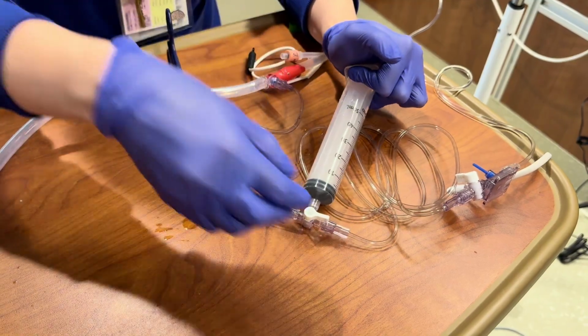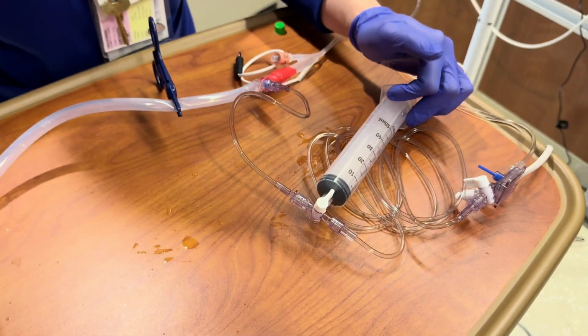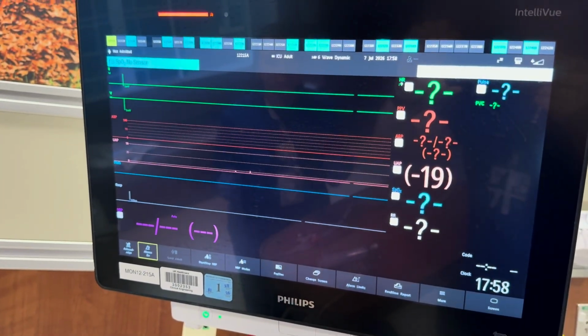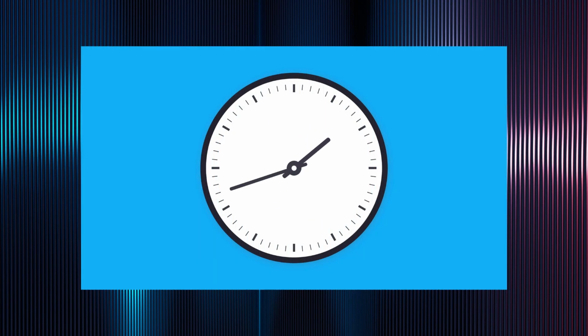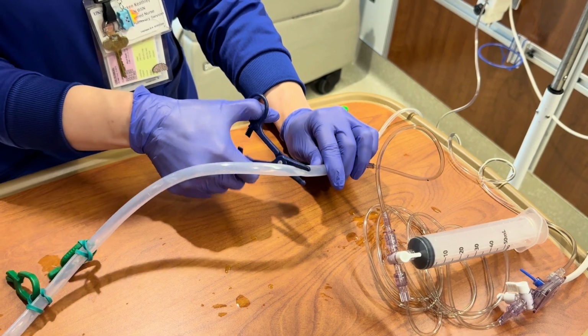Turn the stopcock off to the syringe, and leave the catheter tubing clamped while you obtain your reading. For an accurate reading, wait about 5 seconds and always measure at the end of expiration. Don't forget to unclamp the catheter.